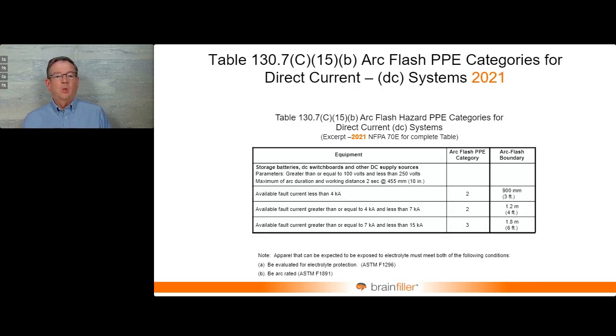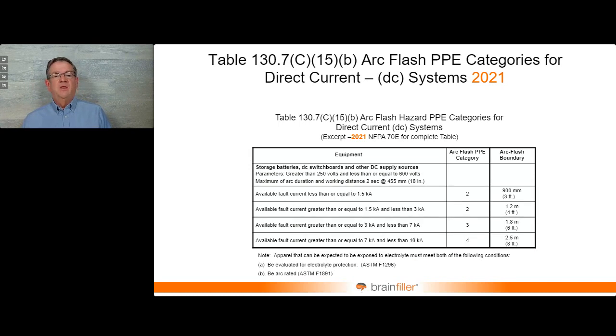So there were two tables in the 2021 edition. One for voltages up through 250 volts, another one 250 to 600 volts. This has all been redone. We have one table based on the test data, and this table is for voltages from 150 to 600 volts. And it's broken up by fault current. So DC fault current, you need to know what that would be.